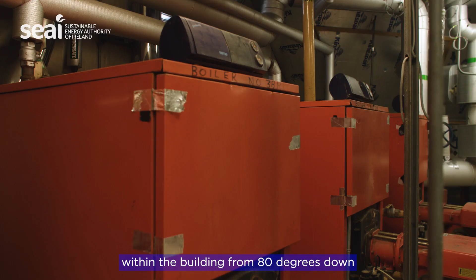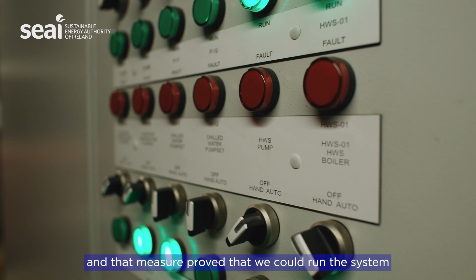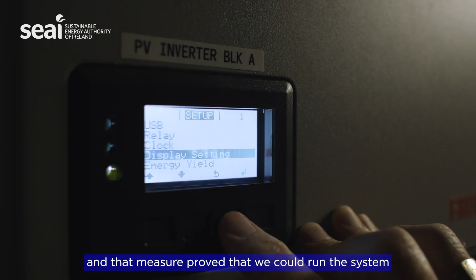We also proved that the existing radiators would work at a lower temperature. We started reducing the water temperature within the building from 80 degrees down to 70, then 60, to see how the occupants would perceive it. To be honest, no one had any complaints - the building kept at 21 to 22 degrees during the day. That measure proved we could run the system at lower temperatures.